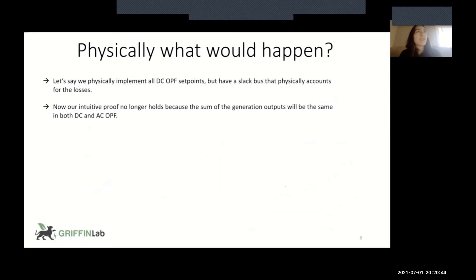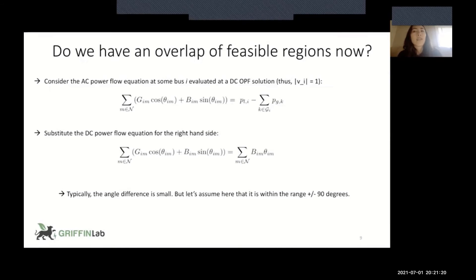Physically, what would happen? So let's say we solve DCOPF. We implement, we send all the generators their set points. They start outputting that power. But we have one slack bus, or maybe multiple. Maybe there's a distributed slack bus, or maybe there's fictitious load that's artificially increasing generation at the bus. And now, for some reason, we have a situation where the sum of the generation is the same in ACOPF and DCOPF. So we can't use our easy proof from the last slide. So if the sum of the generation is the same, now do I have an overlap of the DCOPF and ACOPF feasible regions? So let's take a look at this. And I know I'm going really fast, but I want to make sure I don't go over, because that is annoying for viewers.